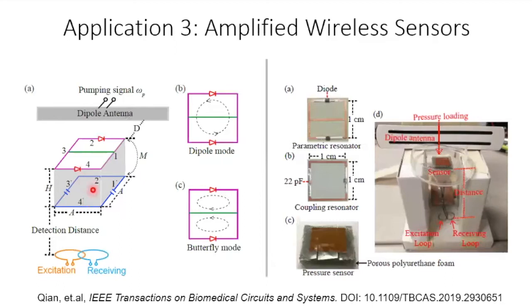So in this diagram, I have listed the circuit diagram of a sensor that we are currently using to measure pressure. This sensor consists of two overlaid circuits. Each circuit is a square loop with one inductor and two capacitors or two diodes. When these two circuits overlay, they have inductive coupling. The coupling strength will modulate their resonance frequency. So if we can read out the resonance frequency wirelessly, then we can translate it to the pressure applied on the substrate.